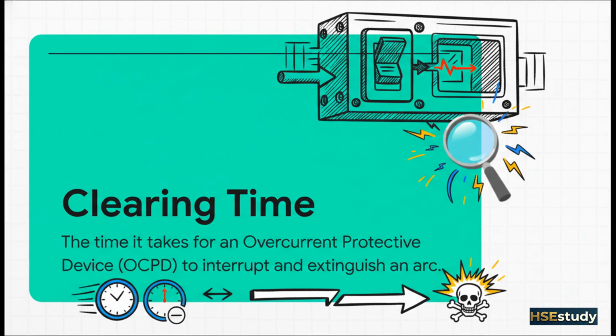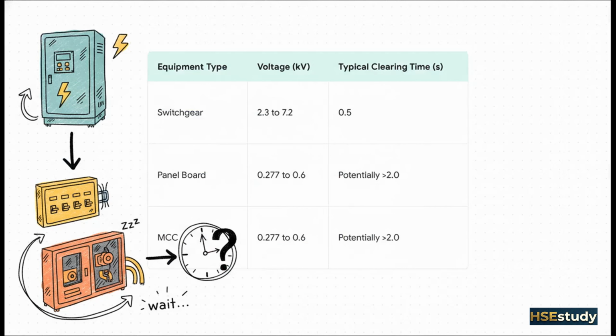Okay, variable number two. And honestly, this is the one that's far more dangerous and far more misunderstood. It's the clearing time. We're talking about the duration of the arc flash itself. How long does it take for that upstream breaker or fuse to finally do its job and kill the circuit? This is where the paradox really becomes a killer. The data on this table tells the whole story.